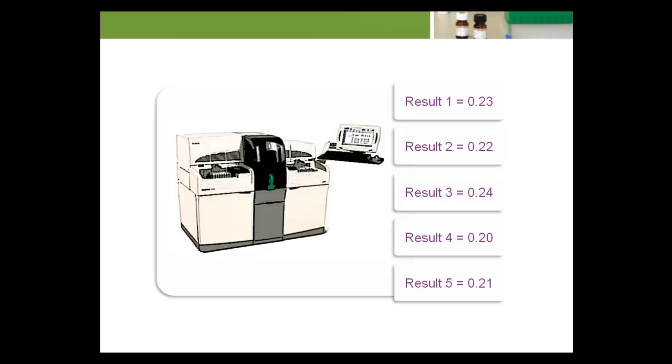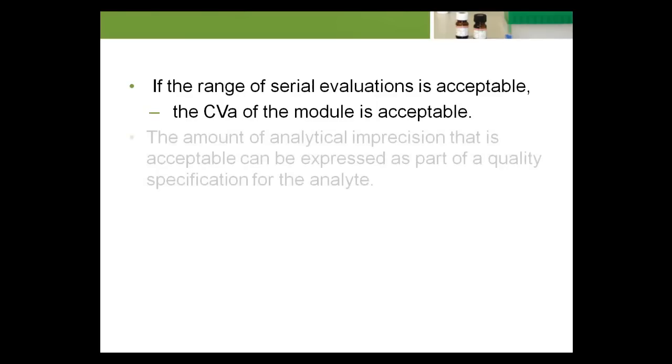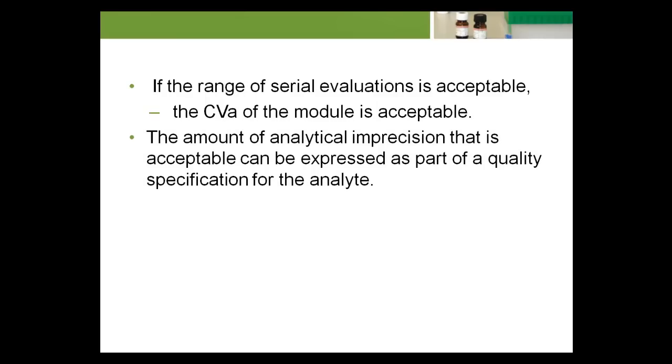The higher the CVA, the greater the range. If the range of serial evaluations is acceptable, the CVA of the module is acceptable. The amount of analytical imprecision that is acceptable can be expressed as part of a quality specification for the analyte.